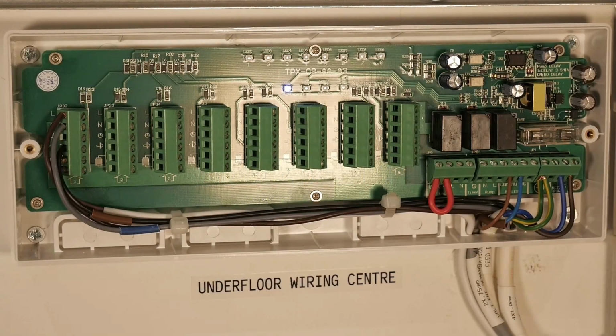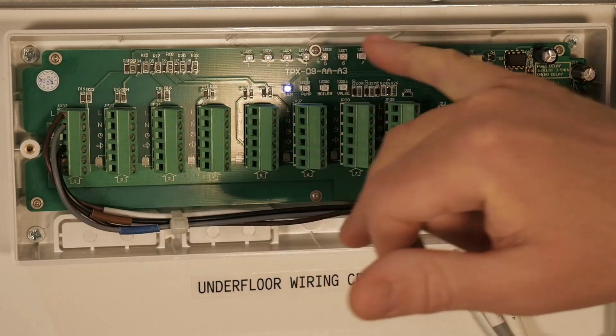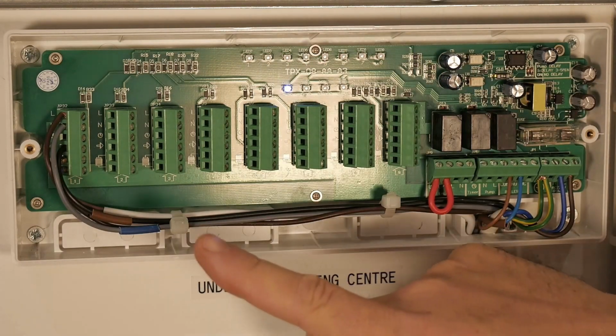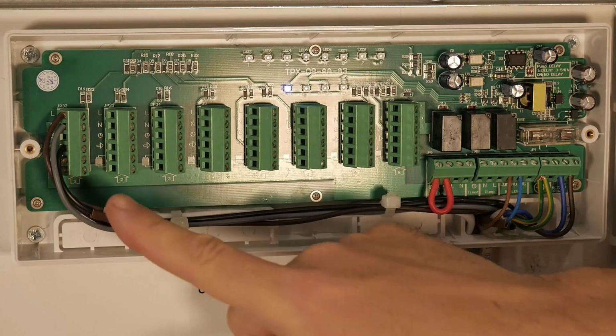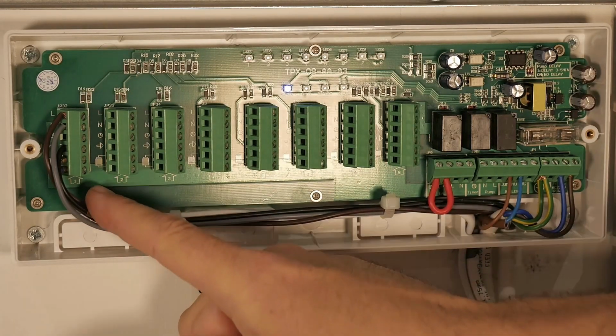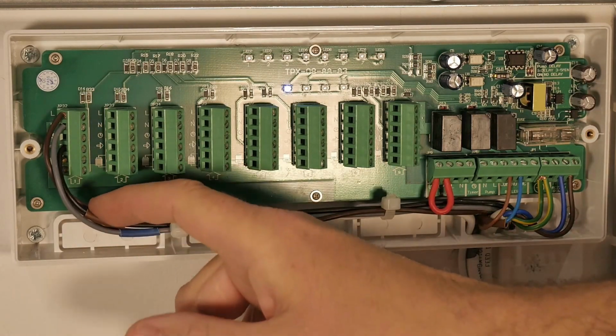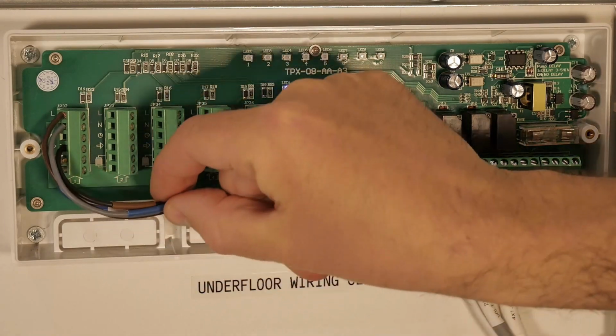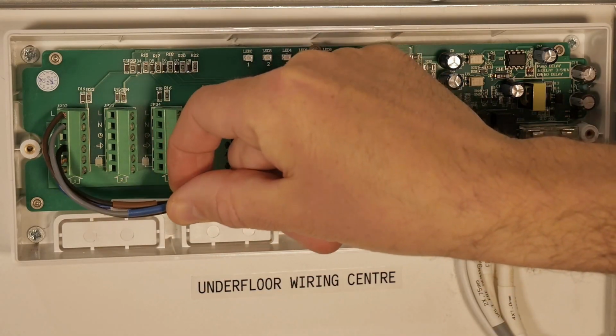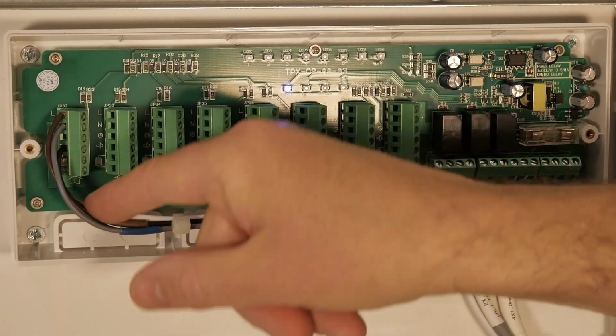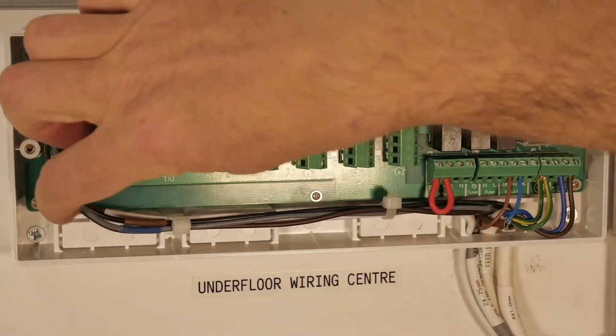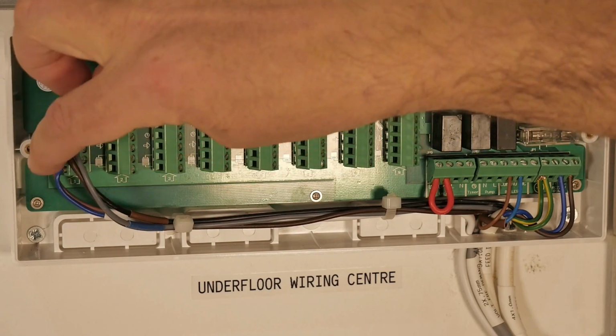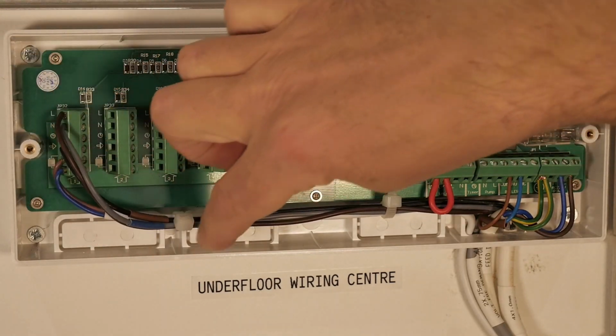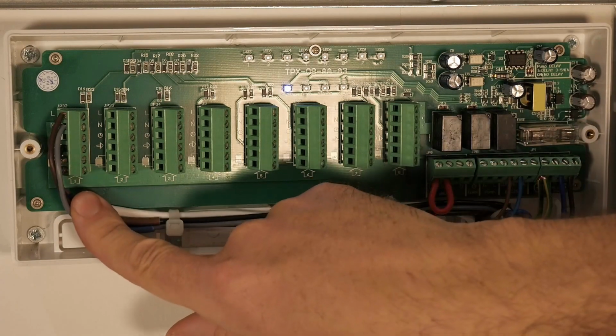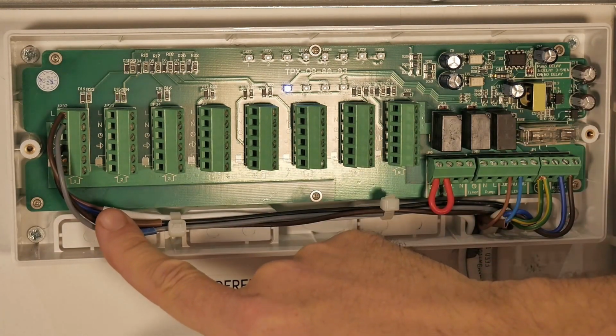Inside the underfloor wiring centre, you can reference the original lights that are on the case cover. Each one of these terminal blocks is for each zone. This is your live, neutral and switch live to and from the thermostat, and the two bottom wires you can see here are the actuator wires, to feed the representative actuator or actuators for that zone.